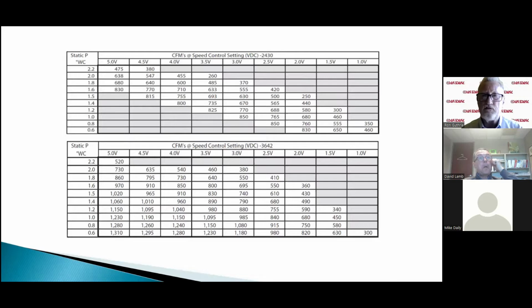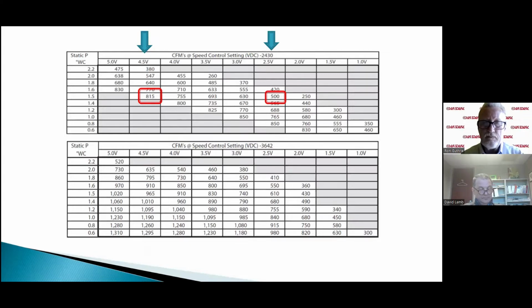I'm going to run through these a little bit here, and the point on this particular chart is that these units come from the factory set about in the middle. So if an installer installed one of these and you're out on it and it's set for 2.5 volts, maybe they never changed it. But they needed to change that if they wanted, for instance, a 2.5 ton and really wanted to be at about 625 CFM, then they really should have switched it up to 3 volts. All right, so that's how you use these charts.